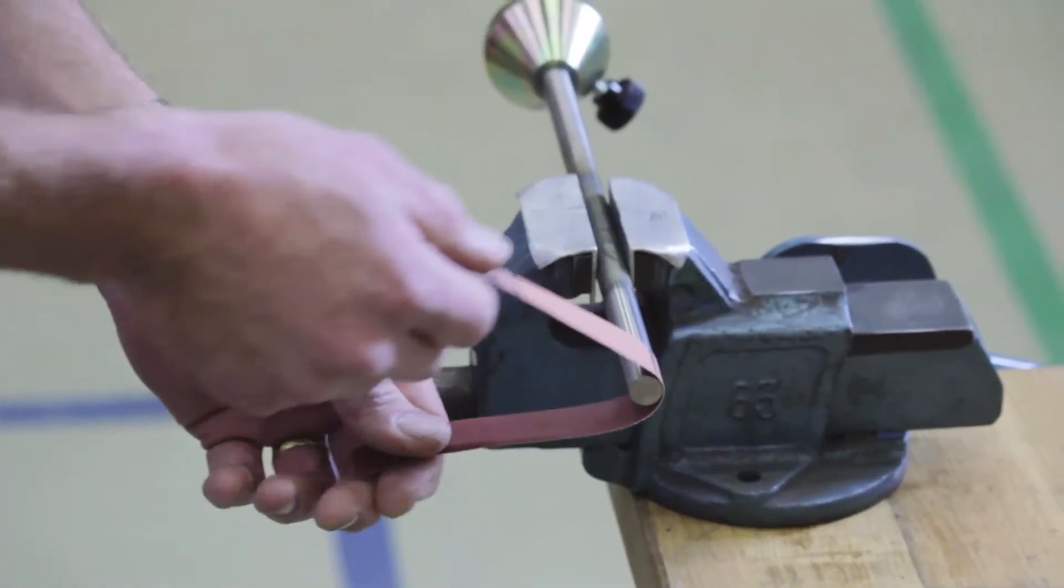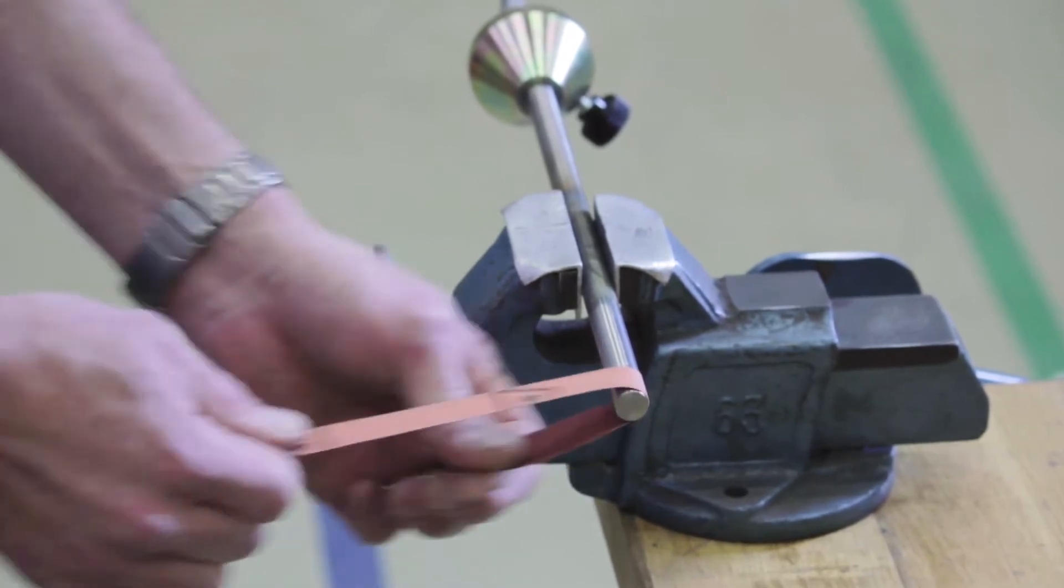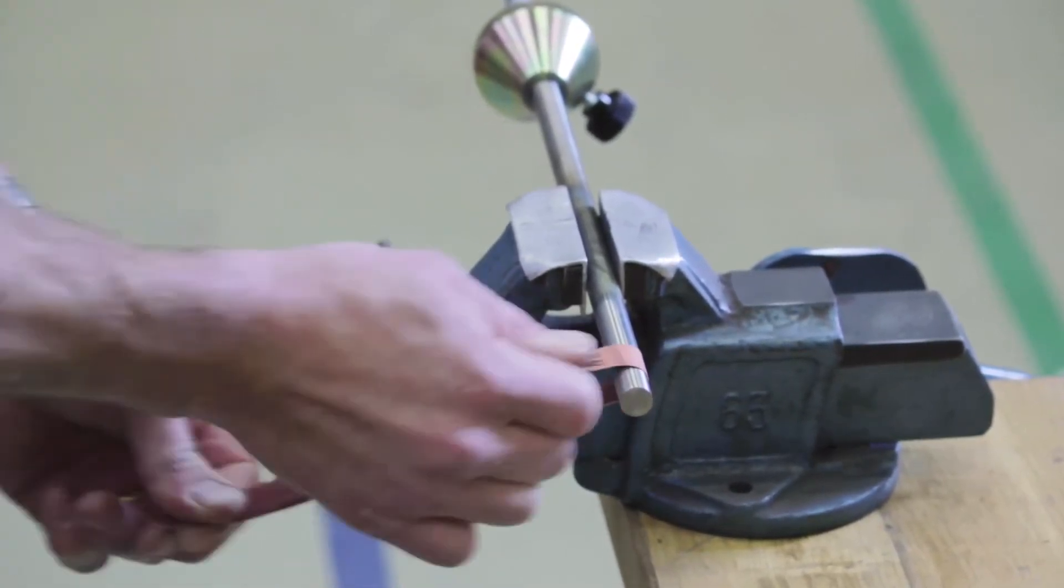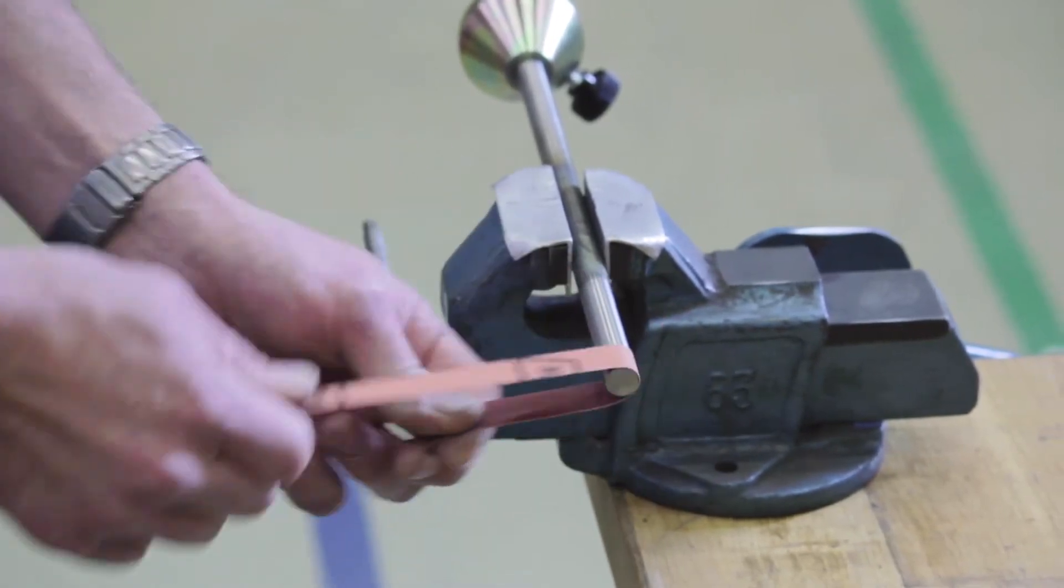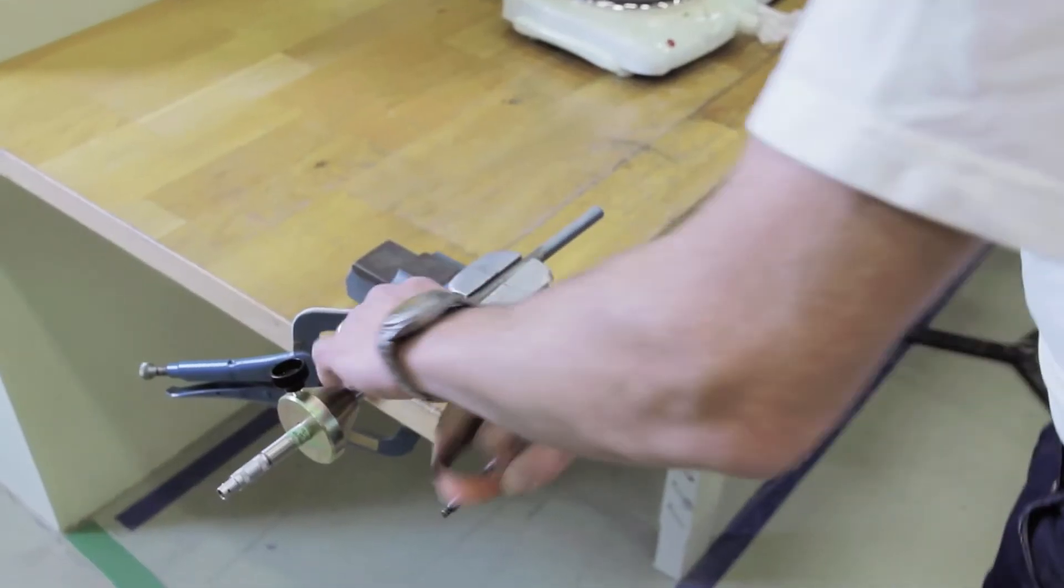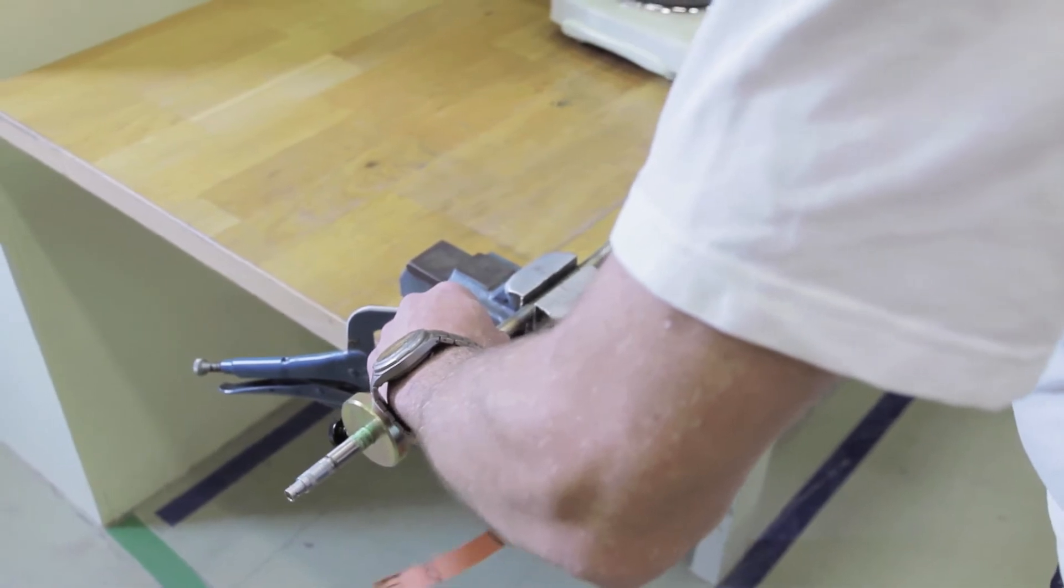When you're finished with the first third, turn the probe one third and continue. Repeat this grinding procedure. Then turn the probe the last third and grind again.